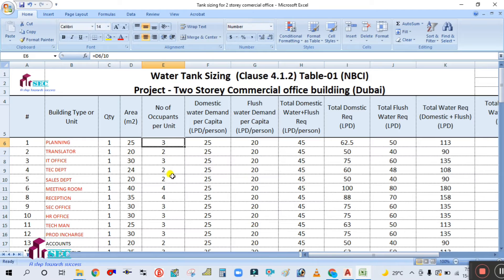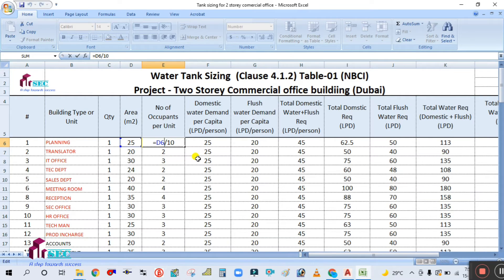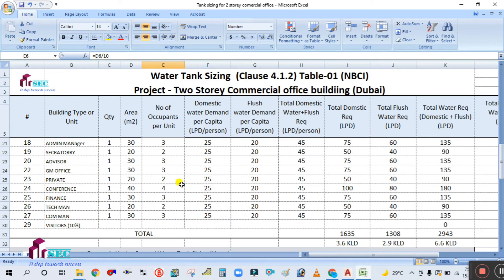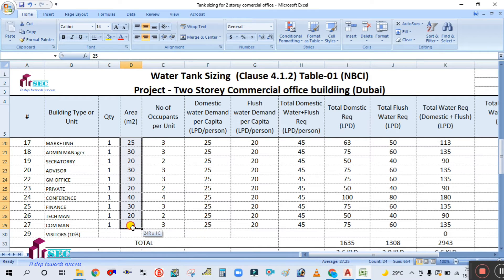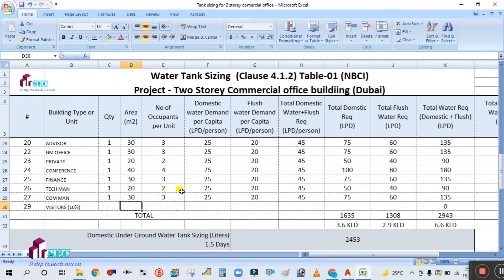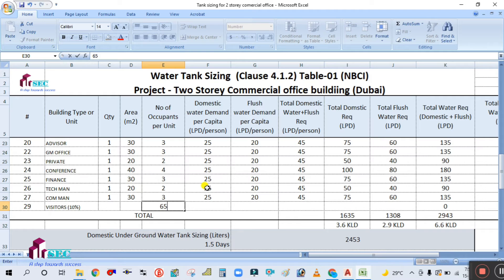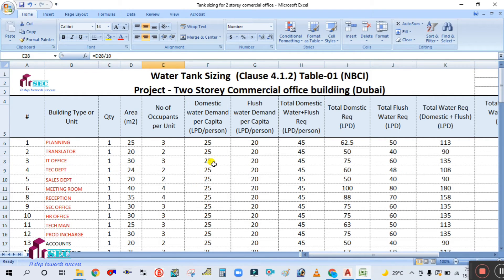Now, number of occupants is based on 10 square meters per person as per NBC 2016 — the National Building Code. Simply divide the area by 10 to get the number of occupants, which is the number of persons. The sum of all occupants across both floors comes to 654, so dividing by 10 gives us the occupant count. For visitors, we take 10 percent — that gives 6.5, rounding to 7 visitors.